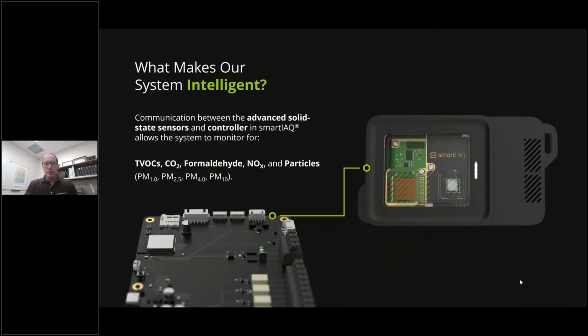So what makes our unit intelligent? Why do we call it smartIAQ? Well, quite simply, it's our ability to do what I call closed loop monitoring, right? We're measuring the quality of that air constantly. And what are we measuring? We're measuring TVOCs, we're measuring CO2, formaldehyde, NOx, and then 4 levels of particles, PM1, PM2.5, PM4, and PM10, right?